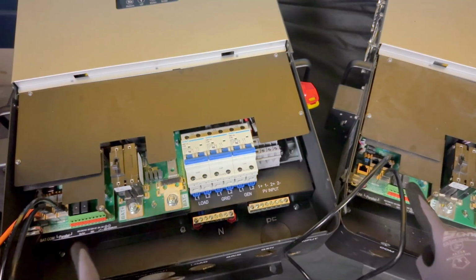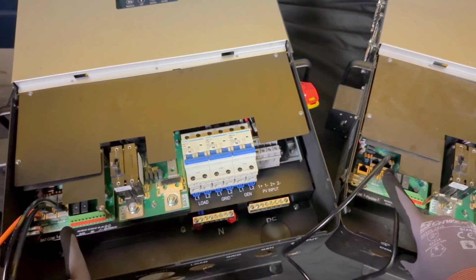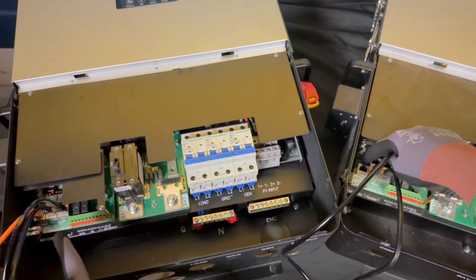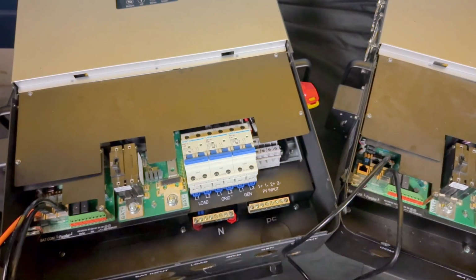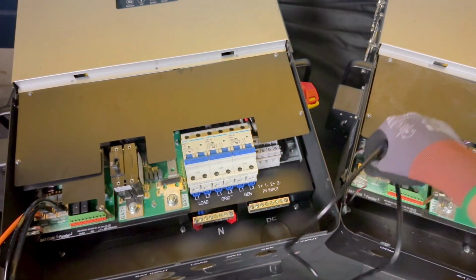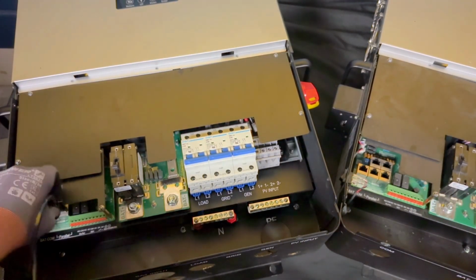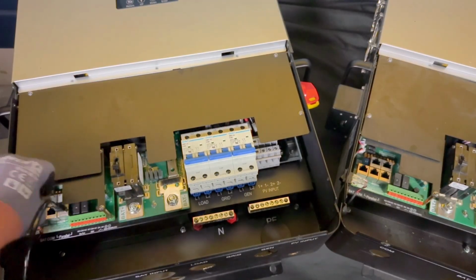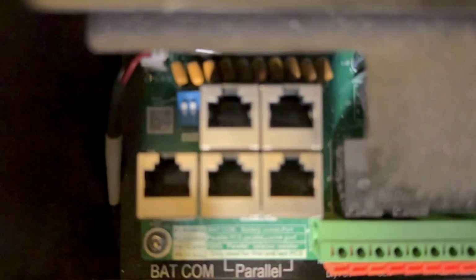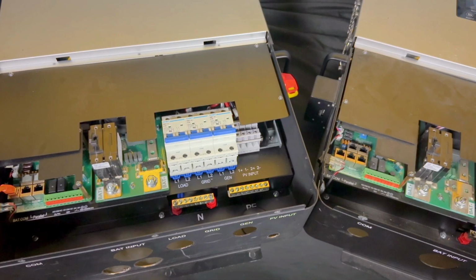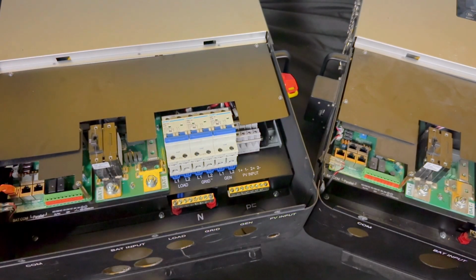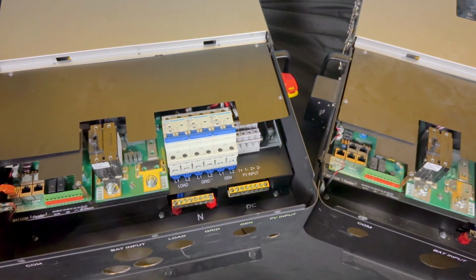The last thing when it comes to paralleling these inverters is to make sure your dip switches are correct. I'll take these guys out right here so we can see a little bit better. So this is my last inverter, this is my master inverter, those are on. Everything else in between needs to be off. Other than that, we are good to go.